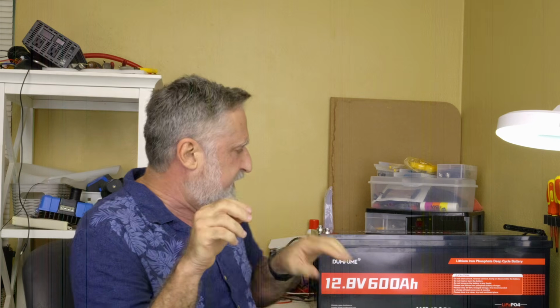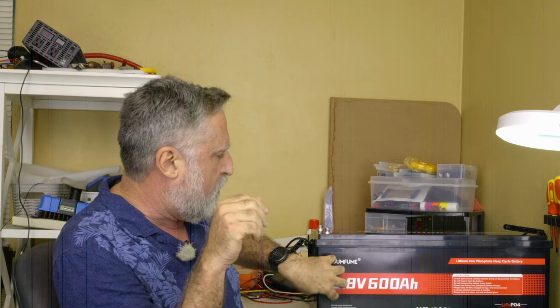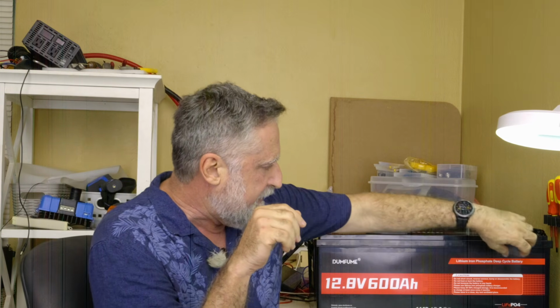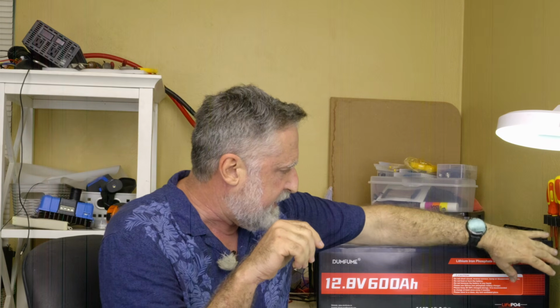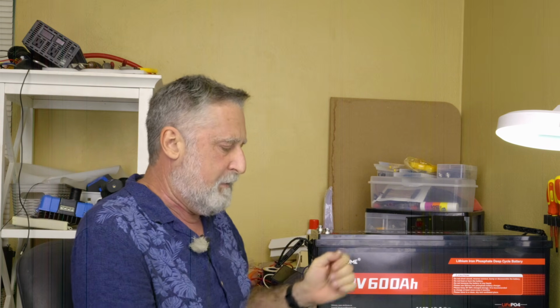It's all down to the rate that they do that discharge at, and even more down to the ratio of that rate to the size of the actual cells. This has four 600 amp hour cells or groups of cells in series, so there are 600 amp hours that have to be controlled. The number is 35 milliamps. I don't think that's enough for a 100 amp hour battery, much less a 600 amp hour battery.